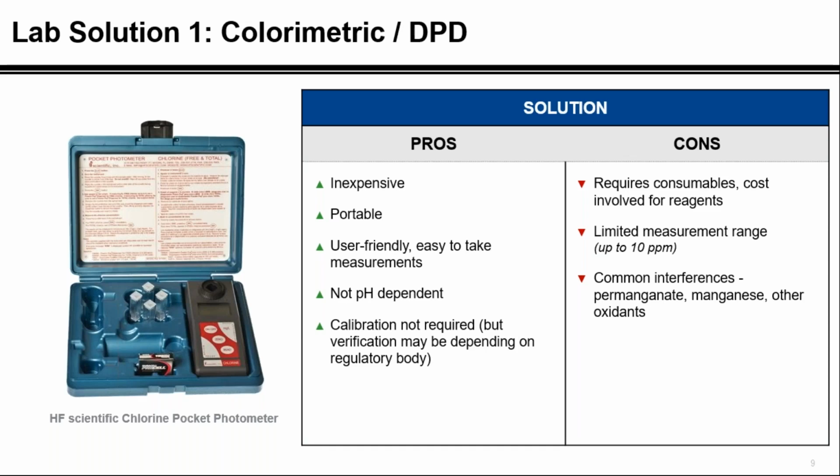Since the chemistry and absorbance stay the same over time and each sample is zeroed before the measurement, this method does not require calibration, but can require periodic verification to ensure correct measurement performance. And I say that generally manufacturers do not require calibration. Please check with your local regulatory body if they do require calibration.